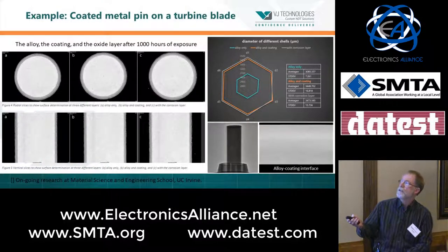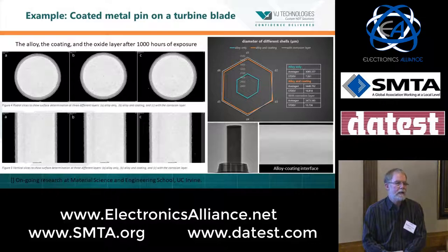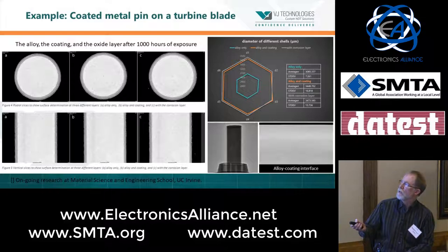This is a pin that's used to hold a turbine in place on a marine gas turbine like the Navy uses for its destroyers. Very harsh environment that it's operating in, very high mechanical stress and strain, and we're measuring the pin holding the blade in place, the pin with a preventive coating alloy over it, and the pin with coating and an oxide layer that's built up on top of it as part of a reliability study. CT can do that.